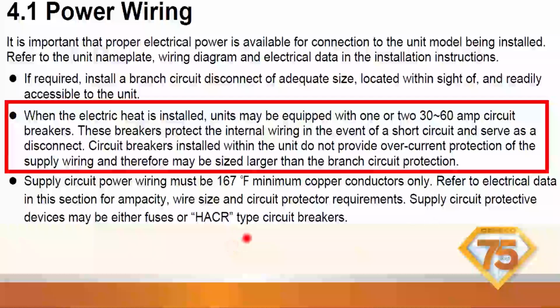Of course, our disconnects. We do have a new disconnect out there by Rector Seal, just so everybody knows. It's a disconnect, it's a surge protector, and it protects against brownouts, because here in the Northwest we're getting a lot of spiked voltages. We're getting voltages of 267 in some areas. Keep in mind, our max voltage for outdoor units is 253. That's a national UL code, 253 max, and we're seeing 267.